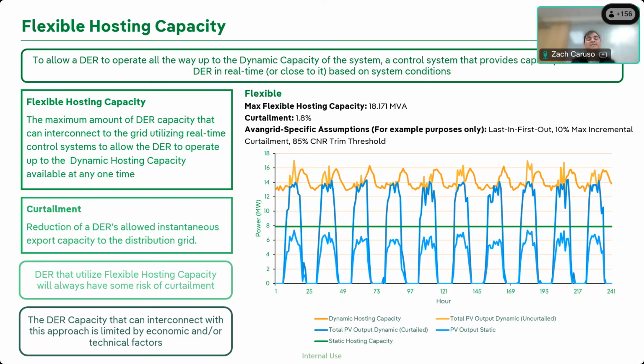And the thing that this does is that it basically, in theory, creates the ability to put as much DER as you want onto a location, because you have a feedback loop that will prevent that DER from going over your system capacity limits. Again, this is assuming perfect performance, but you will always stay within those operating limits because you will always curtail that DER to a safe level. Now, in practicality, it's not practical to install 50 megawatts of DG on a 20 MVA bank because you're just never going to have that amount of capacity, right? Even though I could curtail it and be safe for the developer, it doesn't make sense to have that much capacity on because you're basically paying for capacity that's never going to be able to generate.